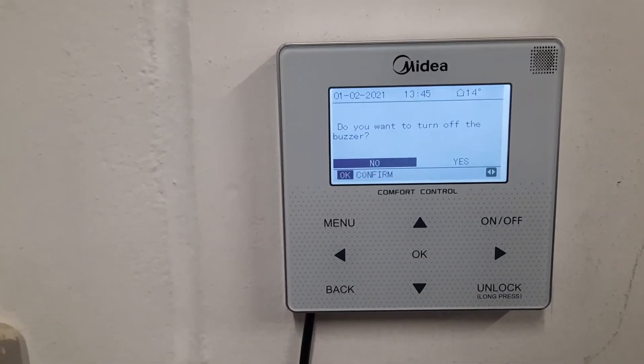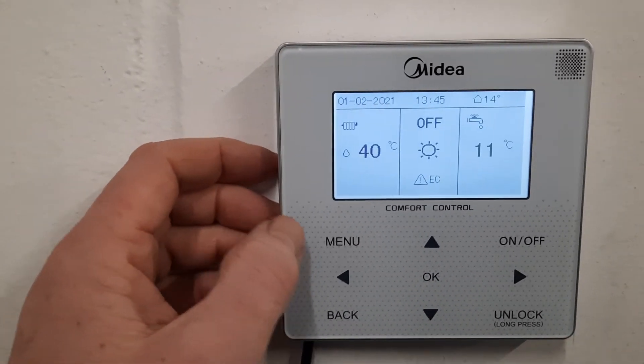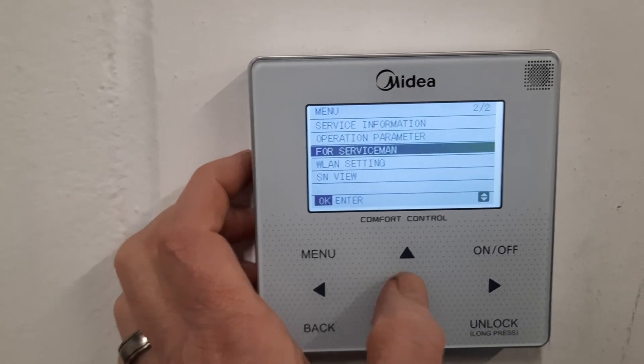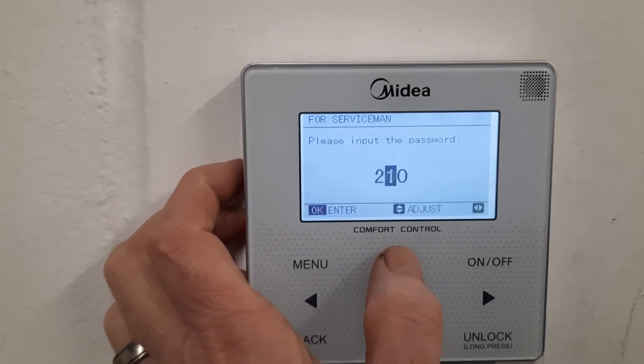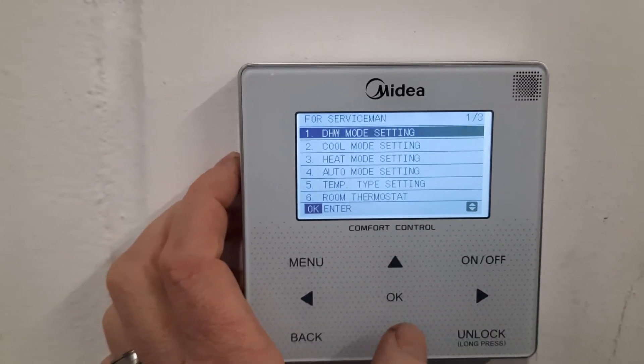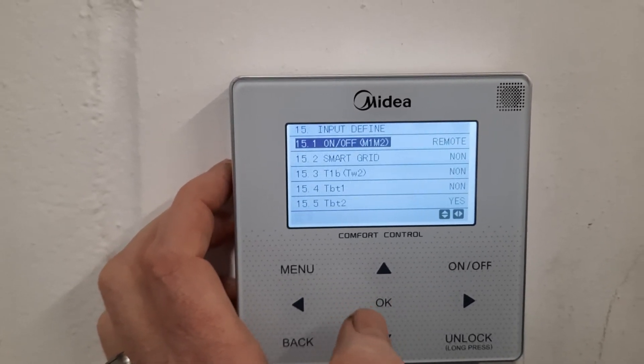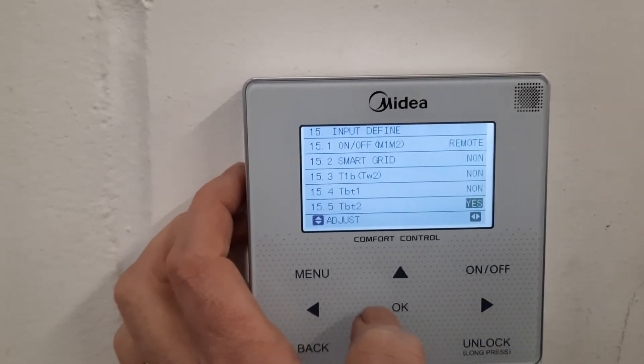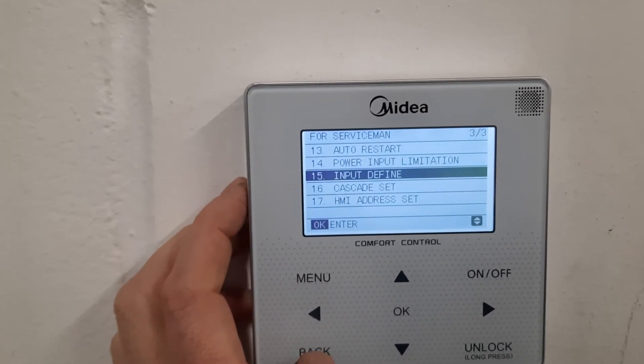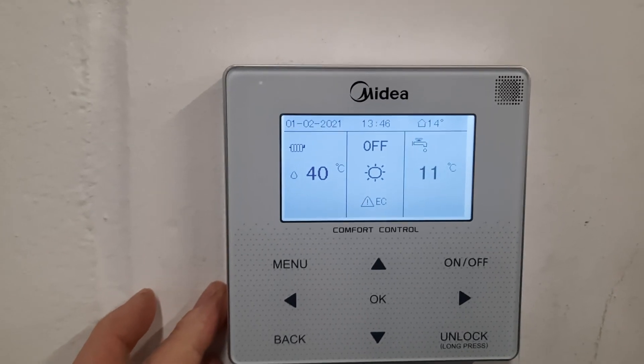Press OK on the screen — it says do you want to turn off the buzzer, press No. We need to go to Menu, scroll down to For Serviceman, press OK. Password is 2, 1, 0. Press OK, scroll down 15 times to Input Define, press OK. Go to TBT2, change that to None, and press OK. Then press Back, back again — it says do you want to activate, say Yes, and the fault code will disappear in a few seconds.